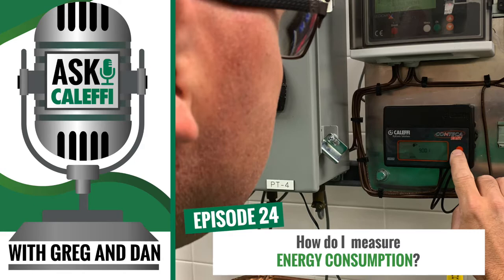That's important — this control is calibrated and to meet the standards it has to be essentially tamper-proof. The sensor leads — I believe they're 20-foot leads on each — are pre-wired into the control and secured in a way that they can't be tampered with. We get the question sometimes: can I extend the wires? But that changes the resistance values, which will throw the calibration off. That's all done at the factory, to keep it from being tampered with.